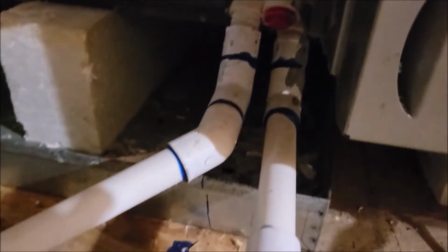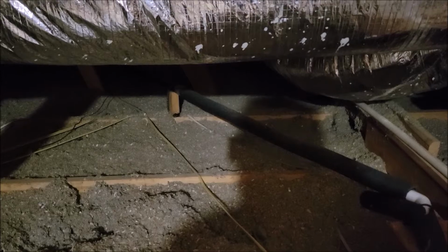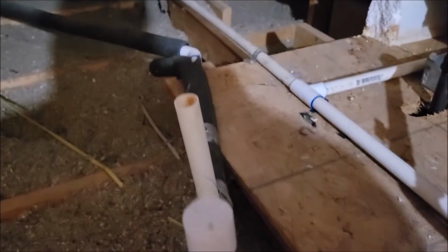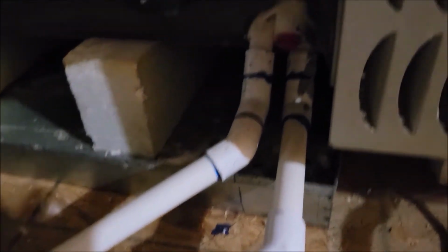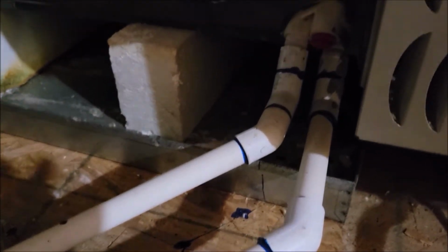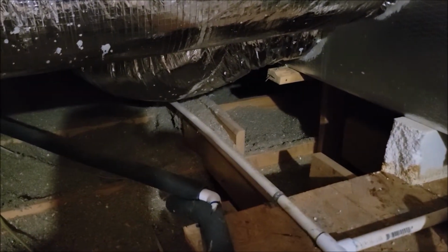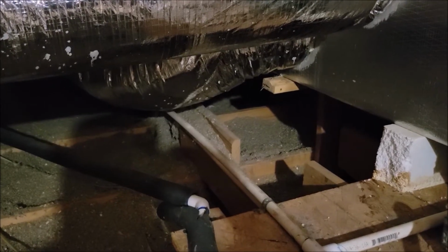So one is here. The lower one is the primary one, which goes this way, there goes the AC unit, goes out, and it connects to a drain in one of our bathrooms underneath the sink. So that's the primary drain. And if that primary drain gets clogged, and it can get clogged in here, pretty much anywhere, then it has a secondary drain, a backup drain, which is this pipe here. And that pipe goes all the way out to the side of the house, and it comes out the soffit, which is what you saw earlier in the video, and that's where the water will drip.